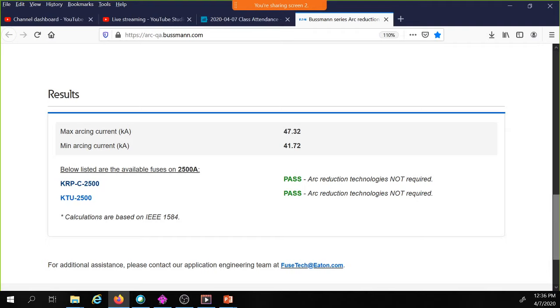And I think as we move along, if you don't understand it now, you will get it as we move along. So what this tool tells you is that the KRP-C-2500 and the KTU 2500 amp fuses will have a clearing time of 0.07 seconds or faster, which you'll learn why that 0.07 seconds number is important. And you do not require an arc reduction technology. So this is just a tool, and I'm going to explain this moving forward. I wanted to make sure you had this.